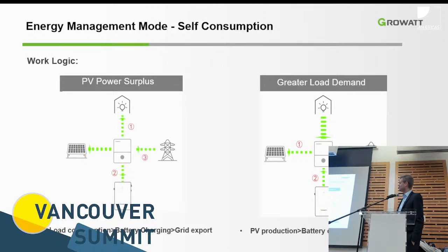PV surplus is pretty much exactly that. So you would typically, in all scenarios, cover the customer's loads first, because that makes the most sense. That's the most efficient from a technical perspective as well as from an economical perspective. PV surplus means first the loads, second the battery, and third, if you still have excess, it goes to the grid. That's pretty much the standard application that you do.